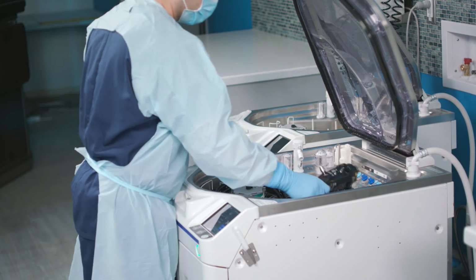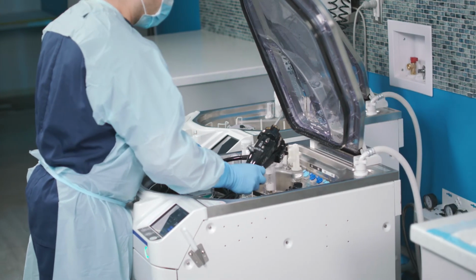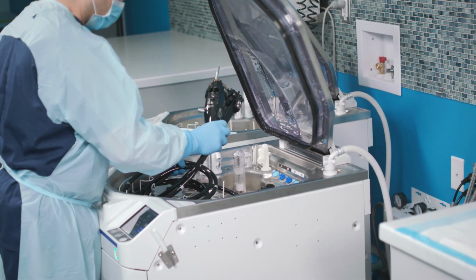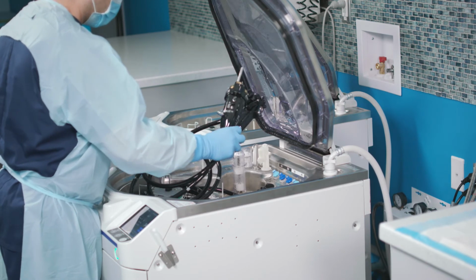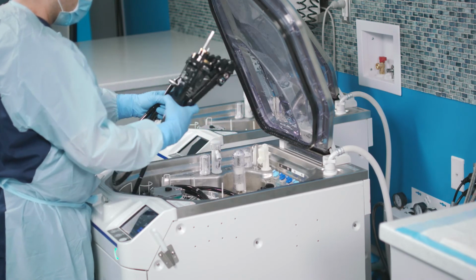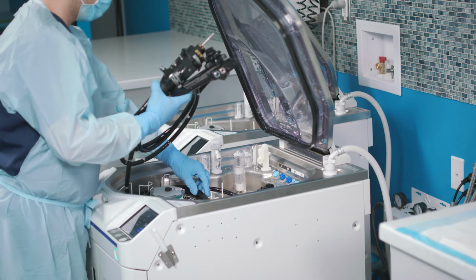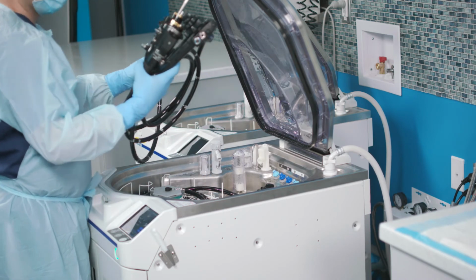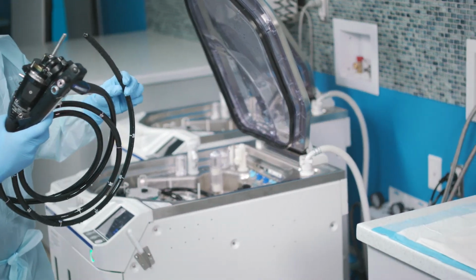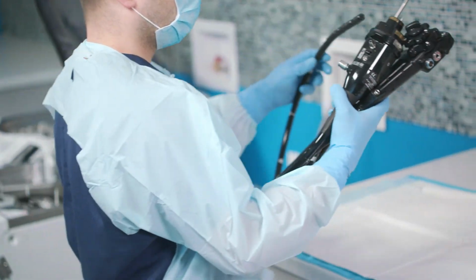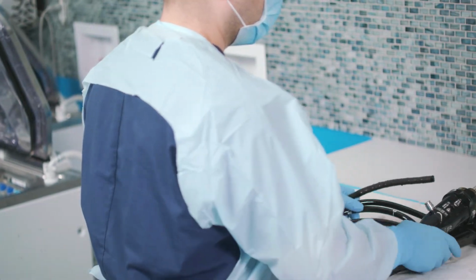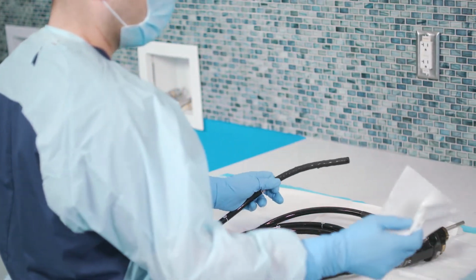Next, remove the endoscopes from the reprocessing basin. Be careful when taking the endoscopes out of the OER-Elite. It is important that the endoscope does not touch any portions of the OER-Elite that have not been disinfected. Finally, wipe off any water using sterile gauze.